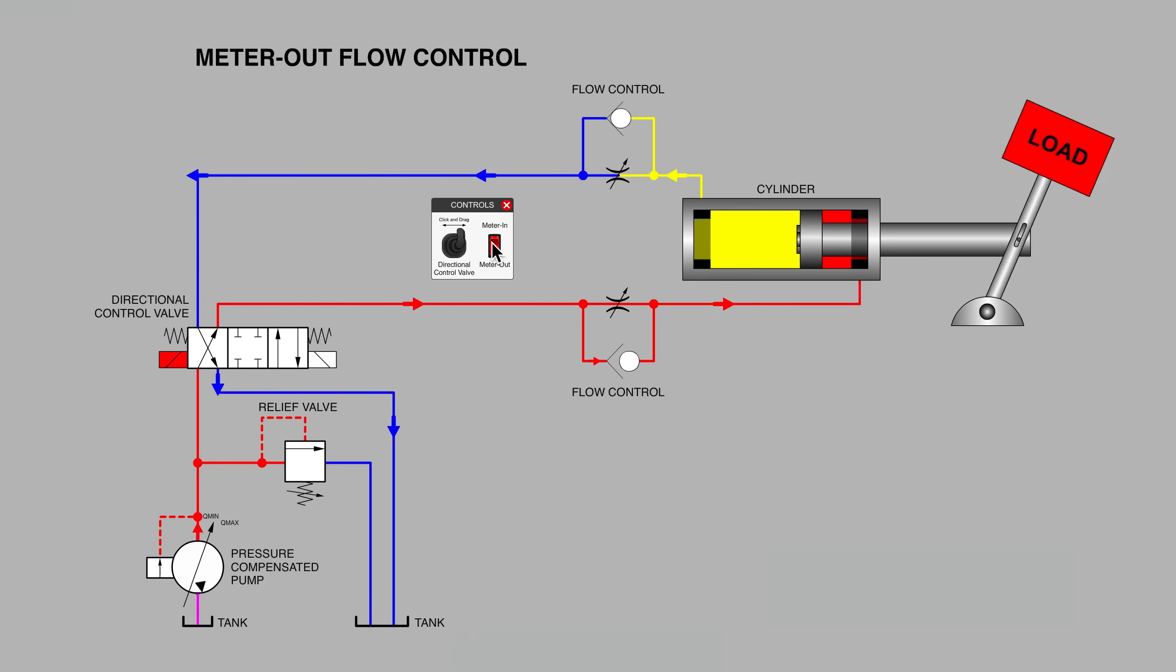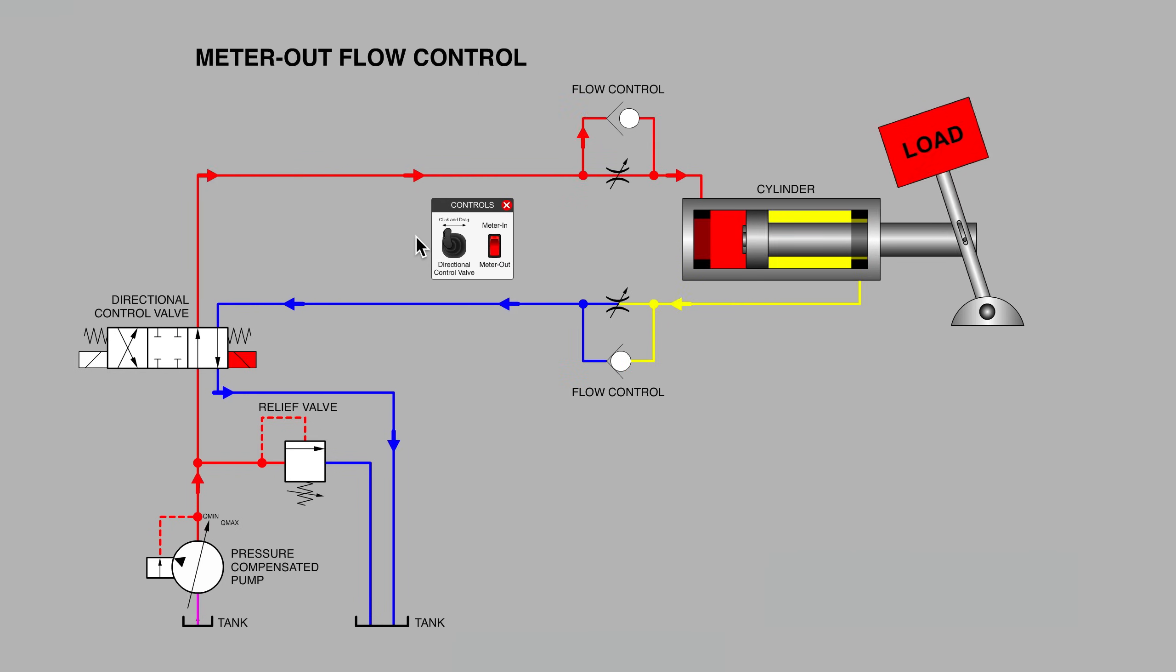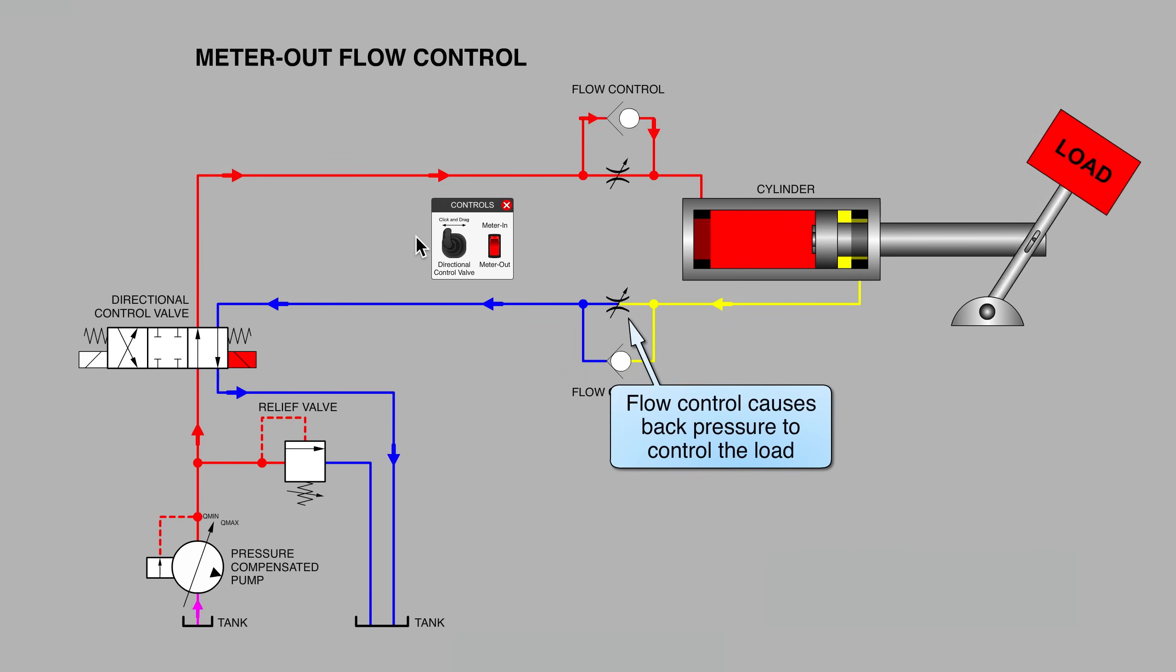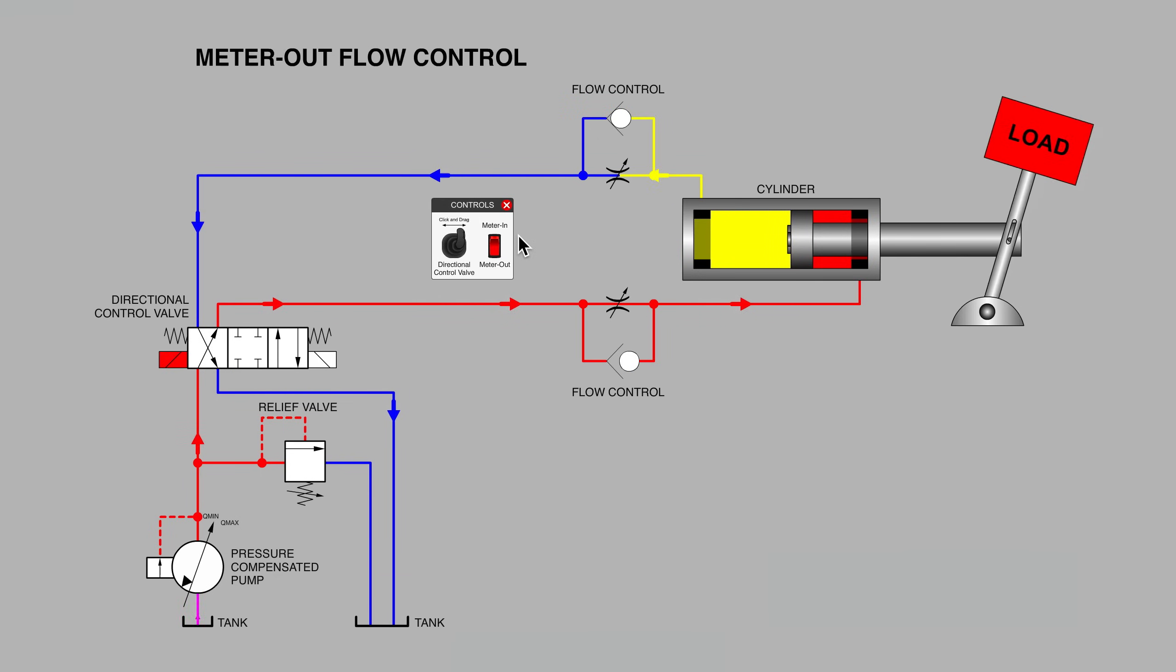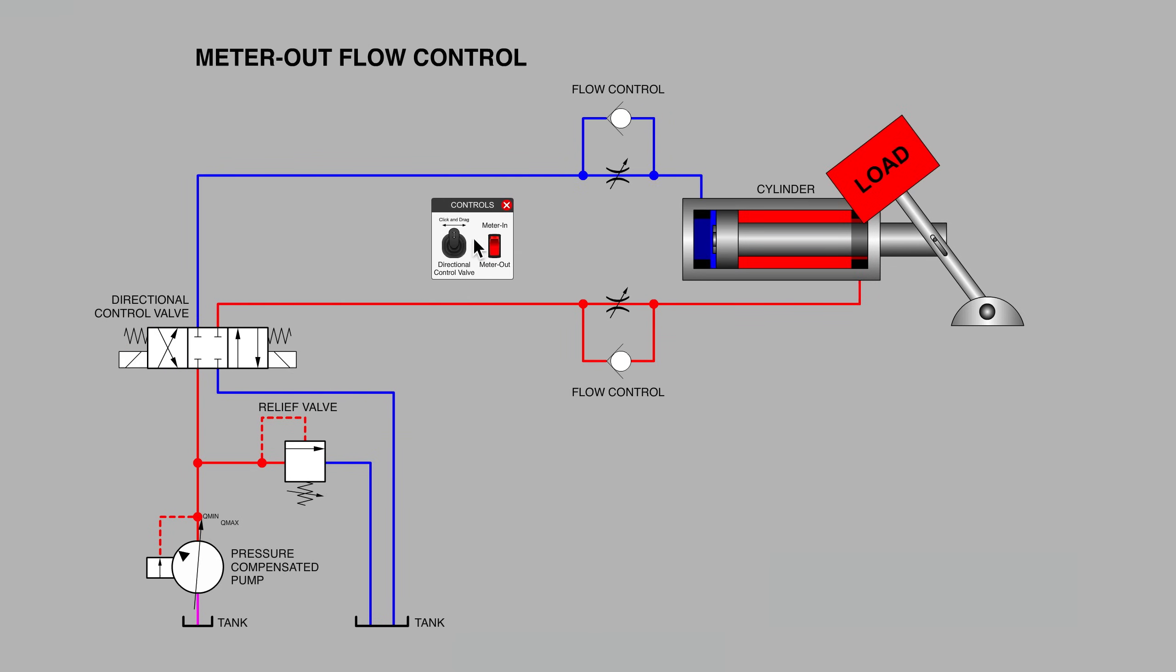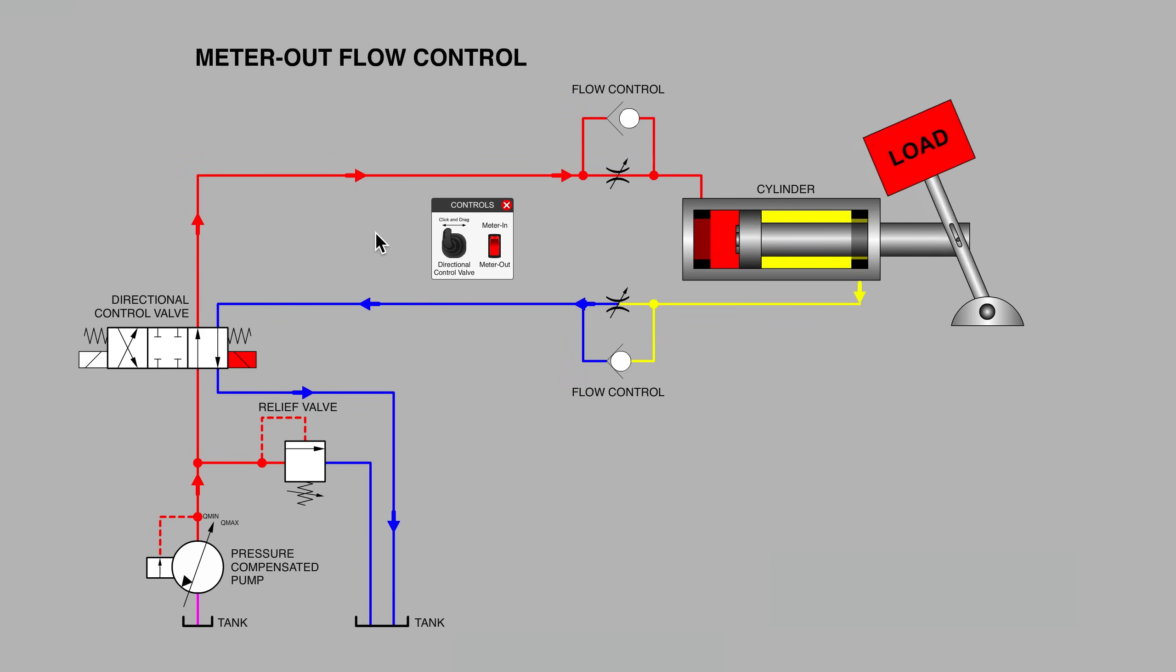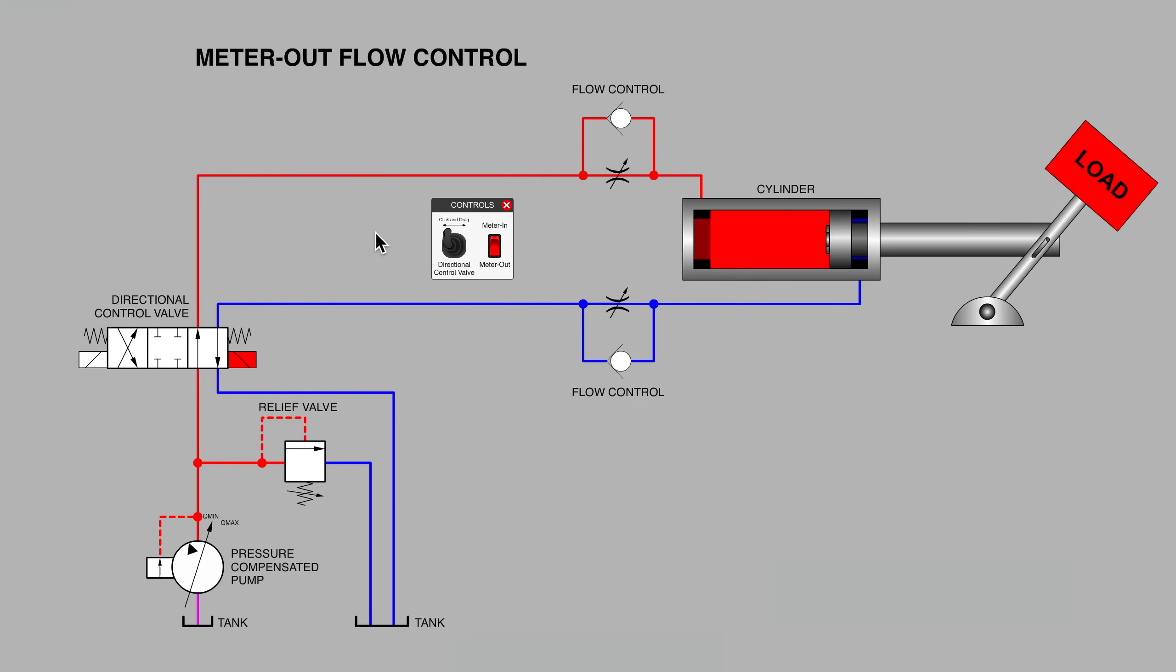And really, whenever there's a runaway load, a flow control is a little overly simplistic. And in many cases, when you need to move the load quickly, a counterbalance valve is a much better choice. And of course, no risk to pressure intensification on the rod side, as long as that counterbalance valve has been chosen and specified correctly.